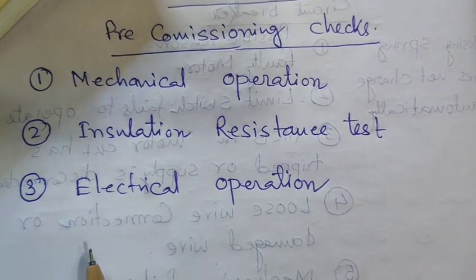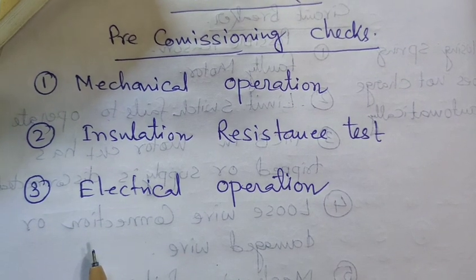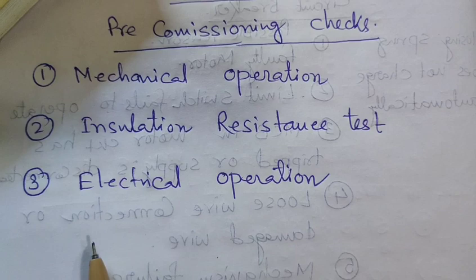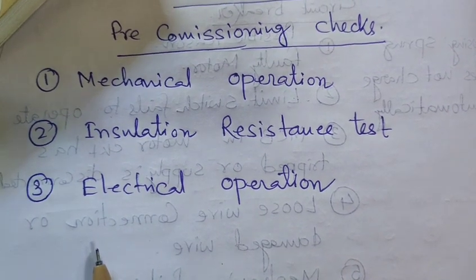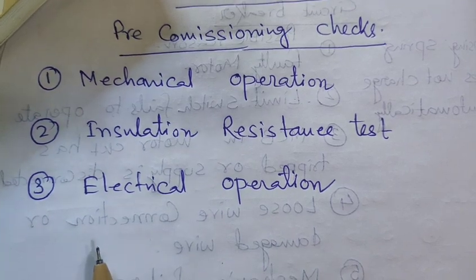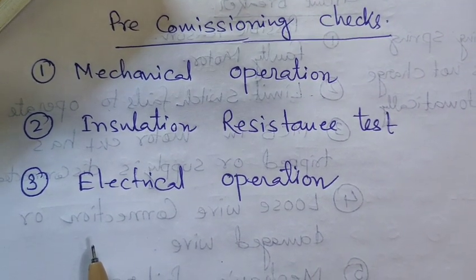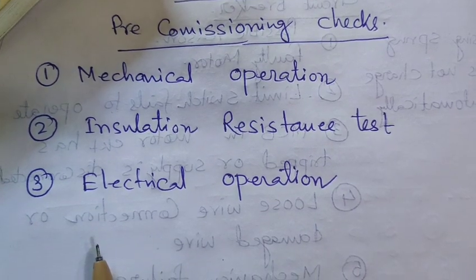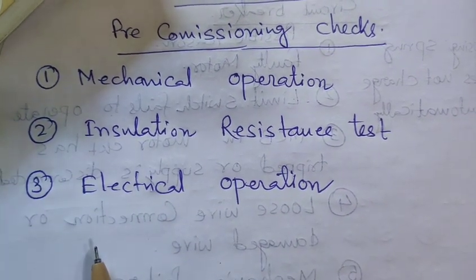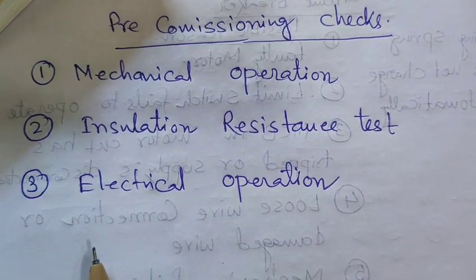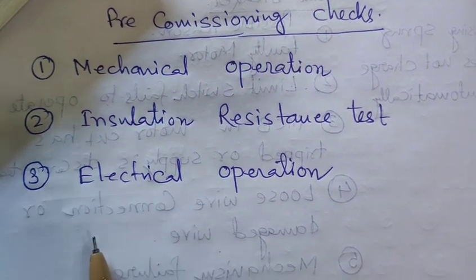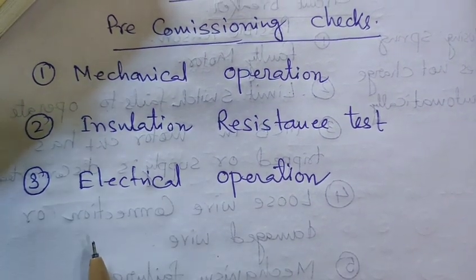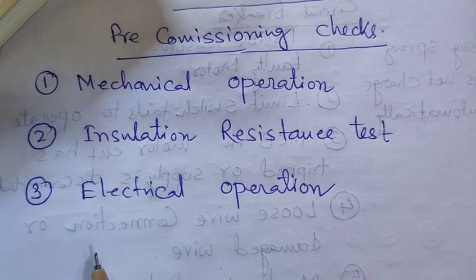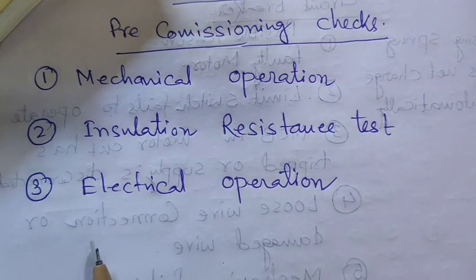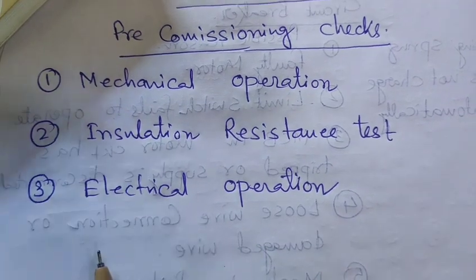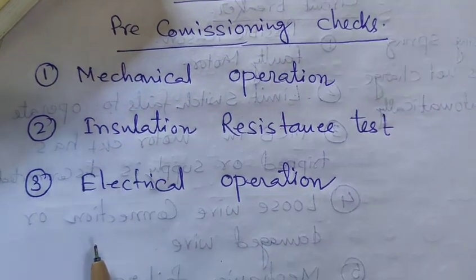If you are confident that the electrical operation is 100%, then consult with the testings, and the testings will recommend that this breaker be put into service. After getting the recommendation from the concerned testings, you can put the circuit breaker into operation for the long time. So these are the three most important types of checking: mechanical operation, insulation resistance, and electrical operation, or pre-commissioning check. You have to remember this, and in your practical field you will be doing these checks before commissioning a circuit breaker for long-time operation.